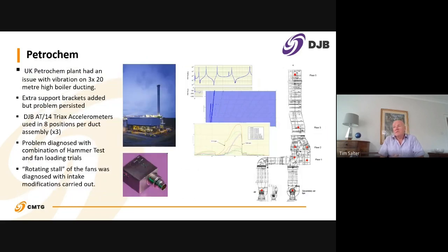And then the final one, this is a petrochem plant, which was a really interesting study of the problem they had. So they had 3 of these, so that's just a generic picture of the plant. They had these ductings over here, which have got 2 motors at the bottom with fans, and then they merge into one. This is around 20 to 25 meters high, because it goes up to floor 5. And they had an issue with vibration.